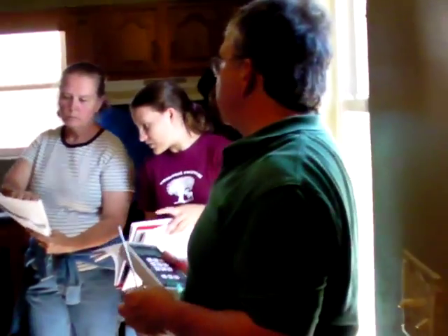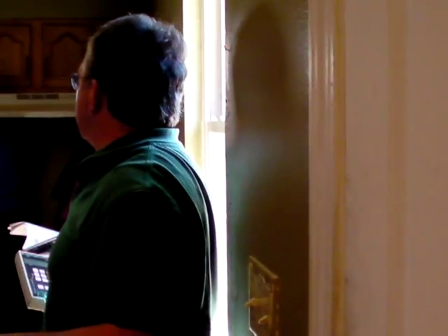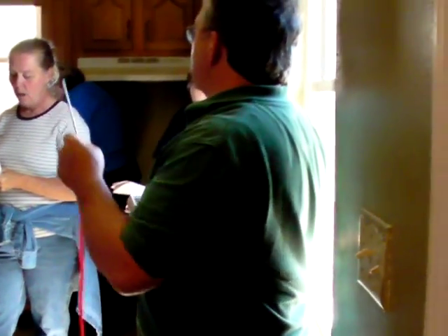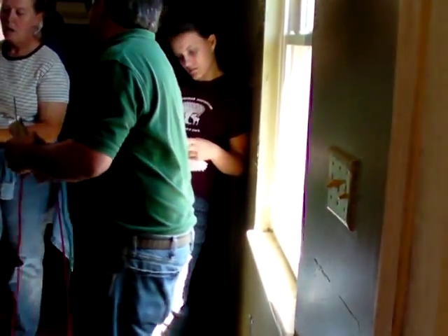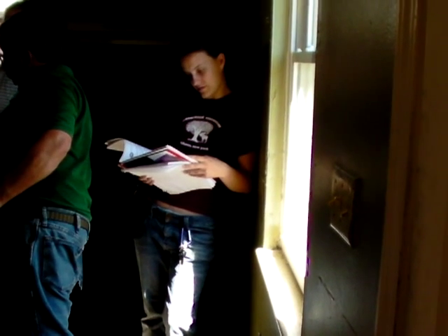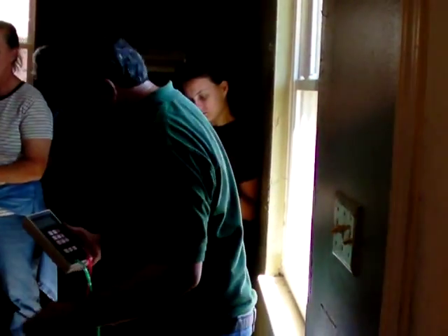If you look at the first item on that list, it says orphaned water heater, -2. Well, right now at this time of the year, since I'm not using the furnace, that acts as an orphaned water heater. But for your field test purposes, you're going to go down maybe 3 or 4, and you're going to see a mechanically induced furnace. Mechanically assisted draft boiler or furnace commonly vented with a water heater. Bingo! Do you see that? -5. Yes. -5 is my limit that I would have when I set up this test.